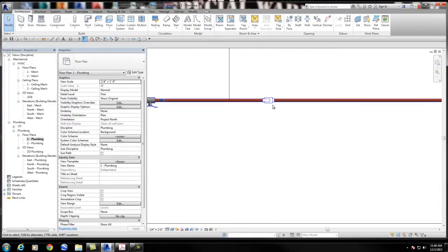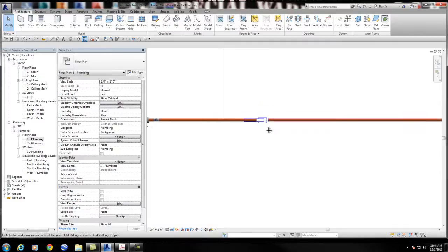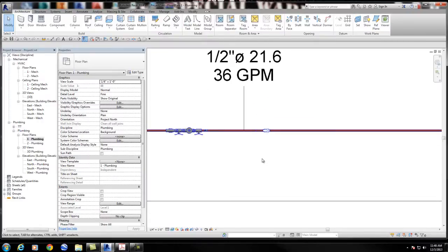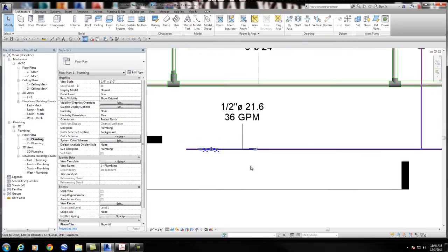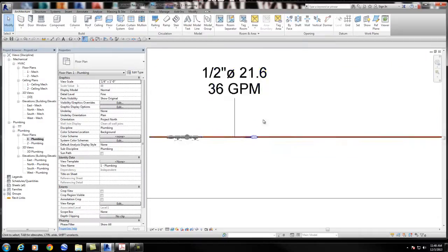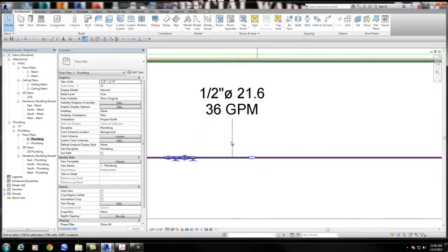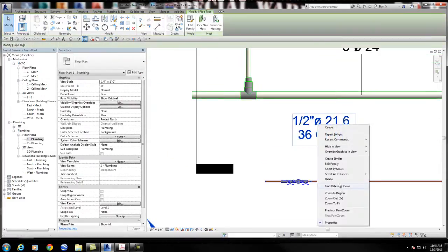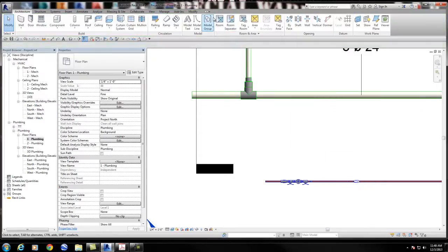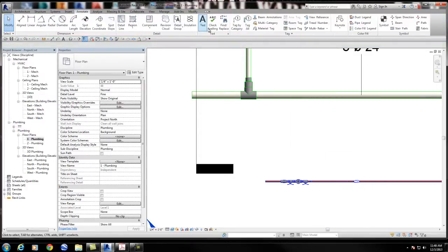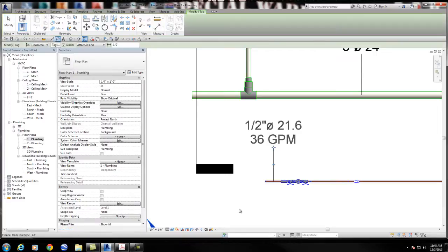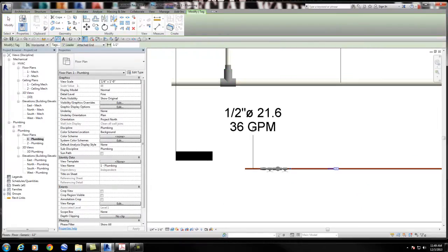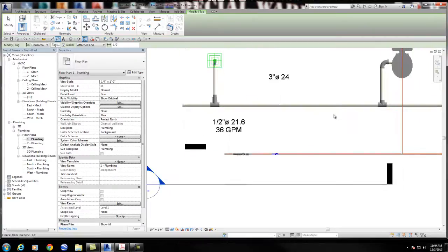So there's a backflow device downloaded from Watts, and they have them in all sizes. Revit out of the box does not have a ball valve that is a half inch or three-quarter inch — I think this is three-quarter inch — so Watts has those available that actually work. A lot of times when people make stuff like that they don't make them properly where the flow goes through, but if I annotate this you can see it's calculating the flow all the way through, which is really nice.